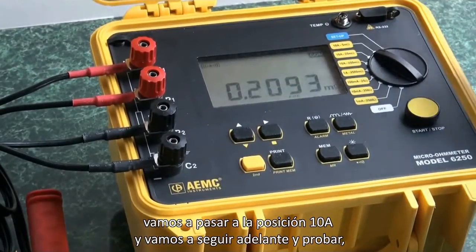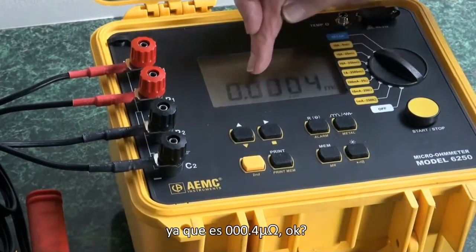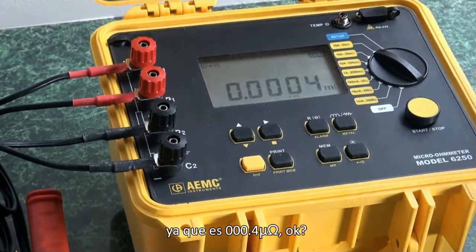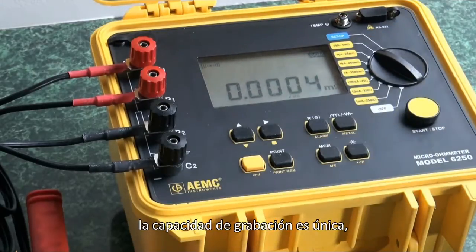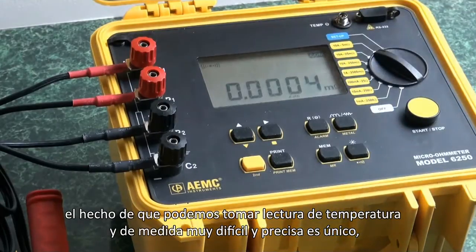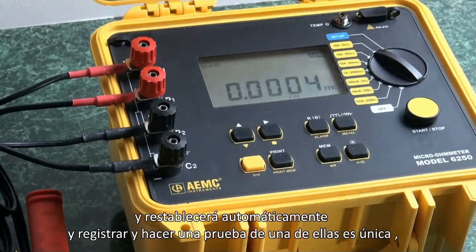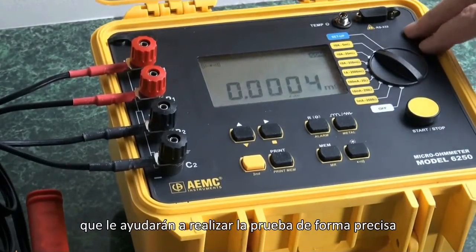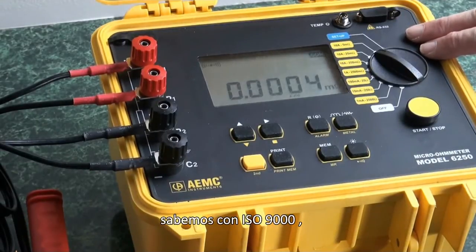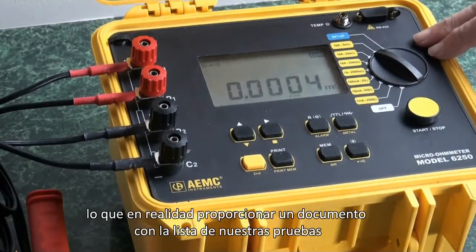Now we'll conduct a new test. We'll move it to the 10-amp position and go ahead and test. This conductor is actually very good because it is 0.4 micro-ohms, which just demonstrates the sensitivity of this meter. The recording capability is unique. The temperature compensation for very difficult and precise measurement is unique. The ability to make multiple tests, automatically reset, log, and test each one is also unique.